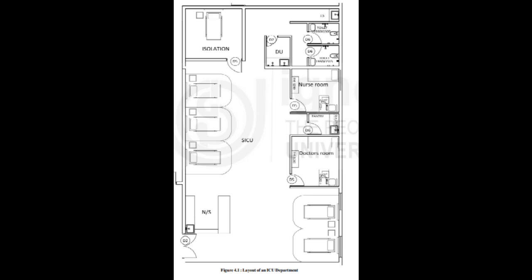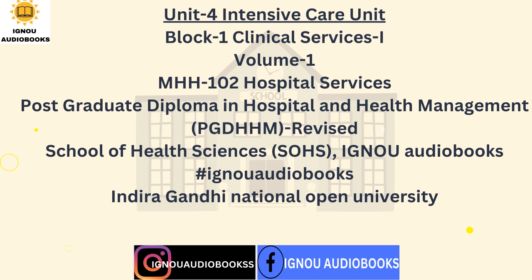For the coronary care area, much more sophisticated patient monitoring is required, which can register arrhythmias and produce both visual and audible signals. The signal should be available at the nurse's desk. In addition to these, physiological recorders for arterial blood pressure and cardiac output measurement by dye dilution technique, by computers and blood volume estimator are preferred.